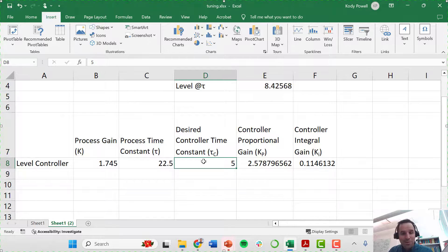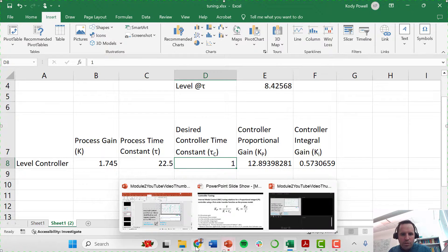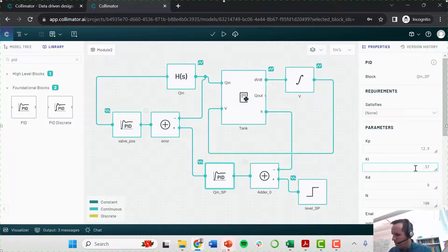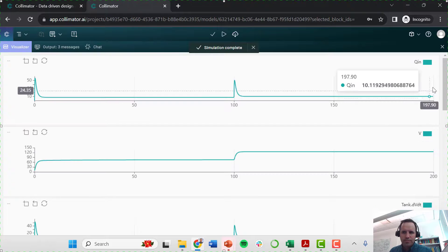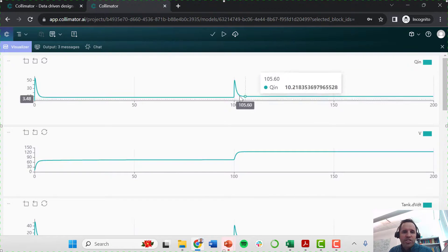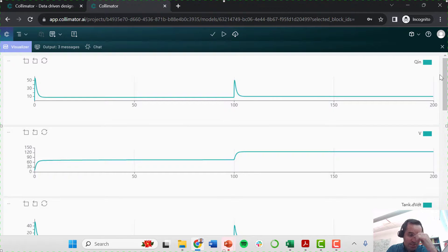Let's change our desired controller time constant to one minute — super aggressive tuning. That gives us a proportional gain of about 12.9 and an integral gain of about 0.57. Updating these parameters in the Collimator model and running the simulation again, we do see the level reaches its new value faster. However, this comes at a cost: the flow rate commanded by the controller rises to about 44 or even 50 cubic meters per minute, which we might not actually be able to achieve in a real system.